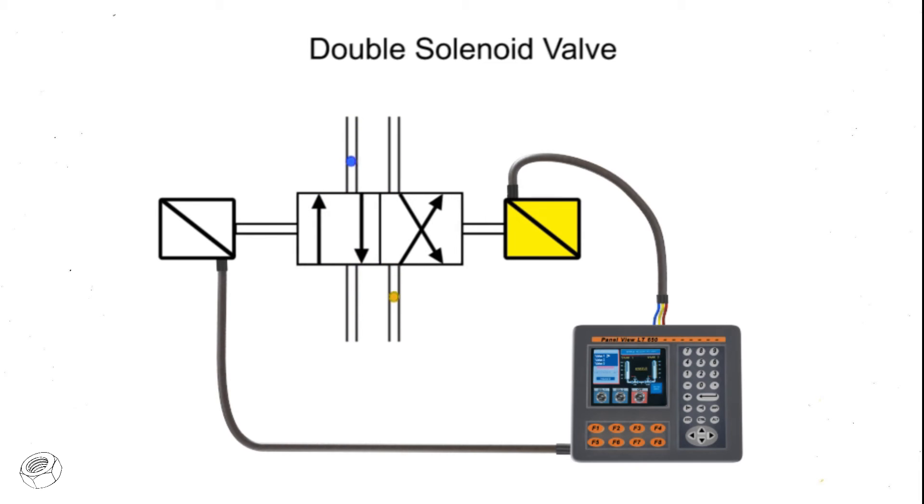Energizing the second solenoid will send the valve to the second position. Even if the second solenoid is de-energized, the valve will remain shifted until the first solenoid is re-energized. Since there is nothing holding the valve in the shifted position other than friction, these types of valves should be mounted horizontally to avoid self-shift due to excessive airflow or vibration. If both solenoids are energized at the same time, the solenoids will work against each other and may cause the spool to become stuck, electrical burnout of the solenoid, or an overload of inrush current to the circuit, any of which will cause severe damage to the system or valve.